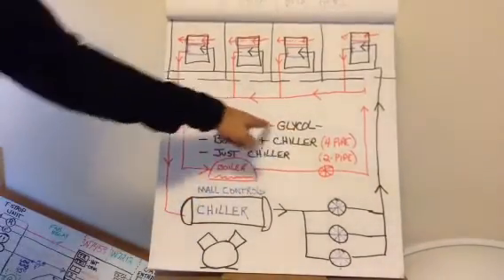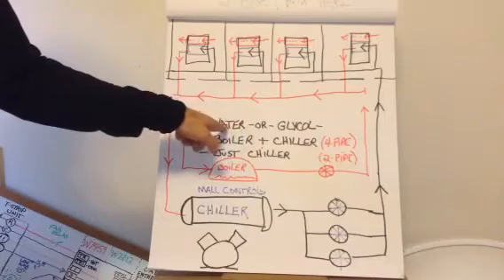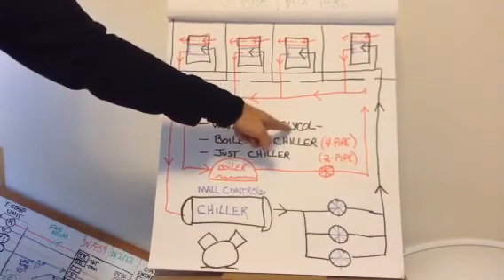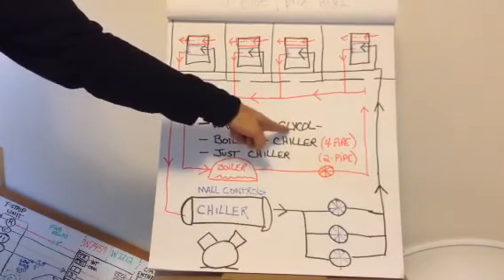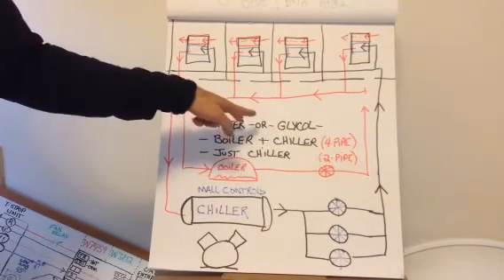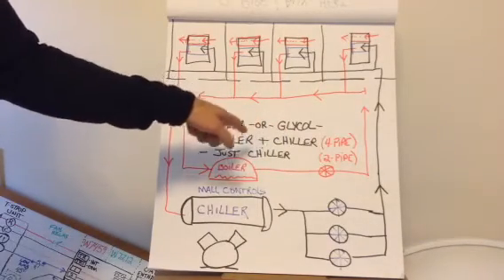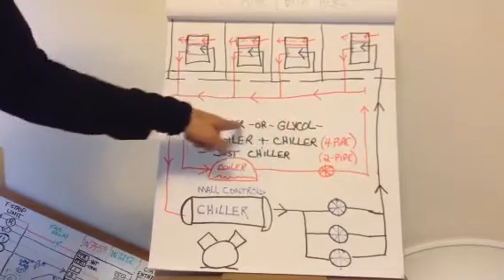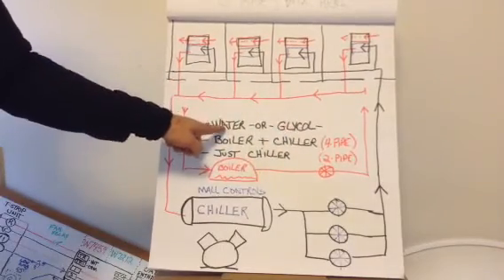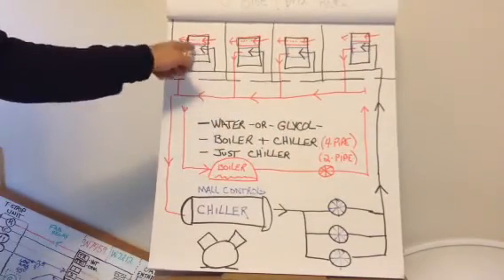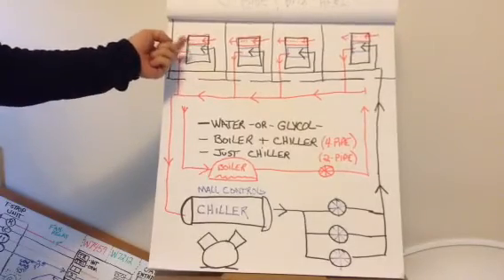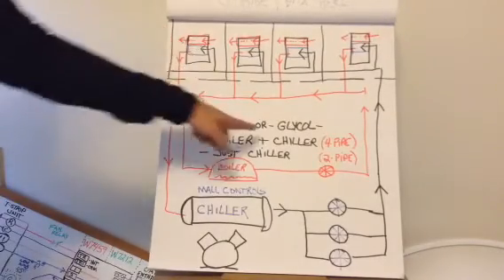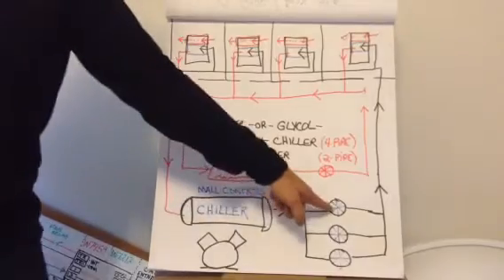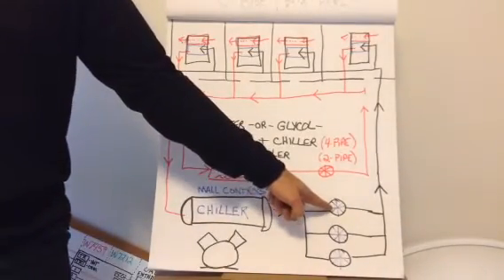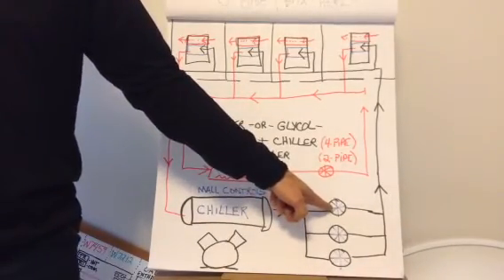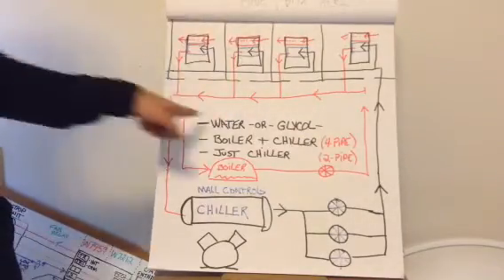The mall also decides if there's water in the pipe, or water mixed with antifreeze, aka glycol, what percentage, and what it's rated to for freezing. Based on this, guys, is also where the mall decides whether we're draining coils in the wintertime or not. Some malls have glycol. They run their recirc pumps in the wintertime on their chilled water when it gets below freezing, so that the water is circulating and they don't freeze up.